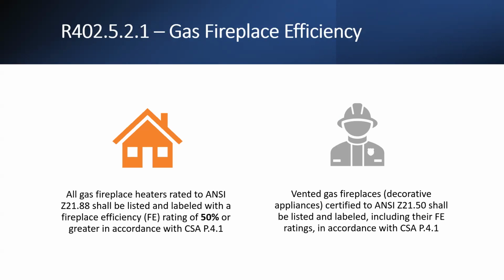That can save a lot of money if you're doing residential style multifamily, and not all of them have to be tested. Gas fireplace efficiencies. All gas fireplace heaters have to be rated by an ANSI standard. It's Z21.88. They shall be listed and labeled, and the efficiency rating, or fireplace efficiency, FE, needs to be 50% or greater according to the CSA P.4.1.